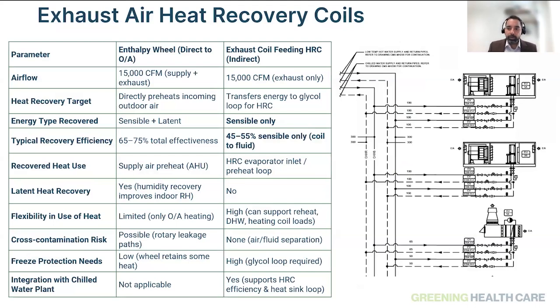Another option, where heat recovery or heat wheels are not an option because of the size constraints or the unit constraints, is to consider heat recovery coils. Heat recovery coils, obviously, as you know, are less efficient than enthalpy wheels. However, they provide more flexibility in terms of recovering that heat and using that heat, now with heat recovery chillers tied into them.